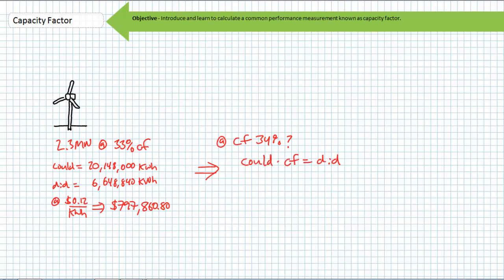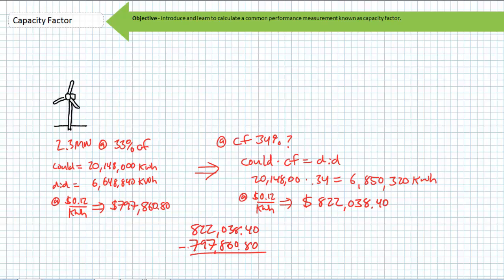In this case, the turbine could generate 20,148,000 times 0.34, or 6,850,320 kilowatt hours. If again you were being credited 12 cents per kilowatt hour, this same turbine, running at an increased 34% capacity factor, would yield you $822,038.40. This is an additional monetary production of $24,177.60 for a single turbine. This is more than enough to fund a handsome bonus for the site supervisor, i.e. you, that is credited for this capacity factor increase.